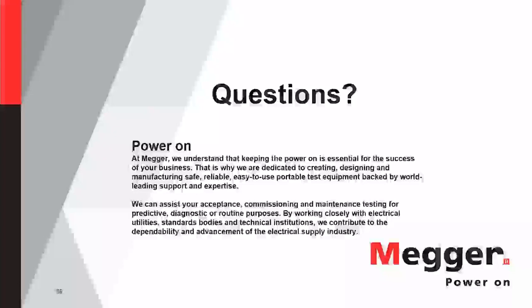Now, when you get to 362 kV and above, the mechanisms don't have enough energy to be able to drive all 3 phases and interrupt all 3 phases at the same time. So now you have a separate operating mechanism per phase. So we call that an IPO, or independent pole operated circuit breaker. So now you hook up a transducer to each mechanism or each phase, and you measure all 3 of those. So really it should be gang operated and IPO kits, but we just call it single phase and 3-phase kit.